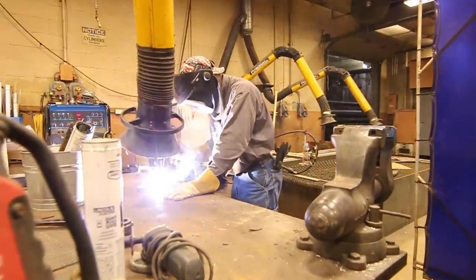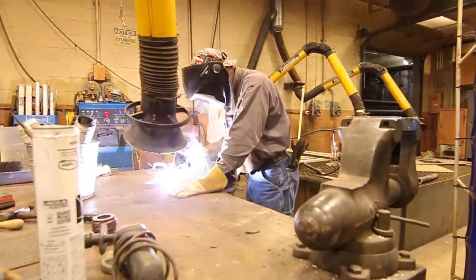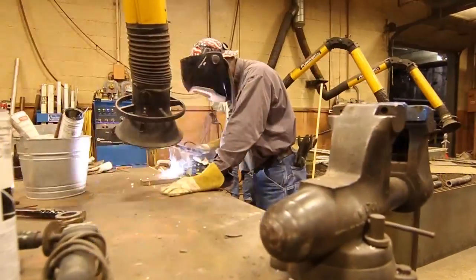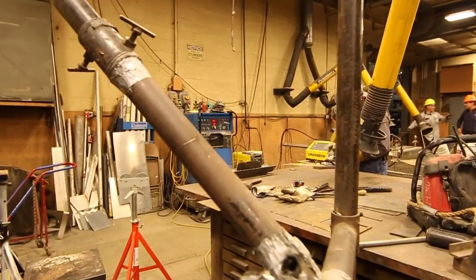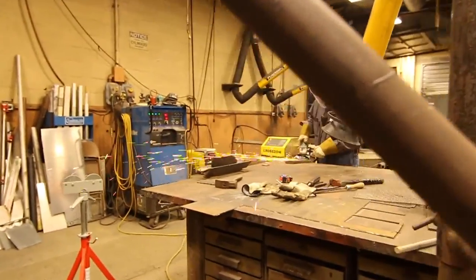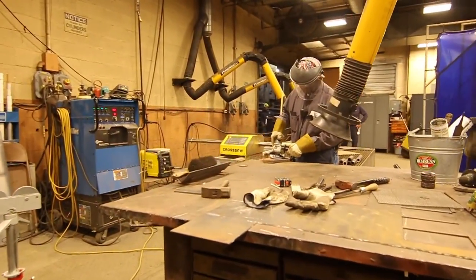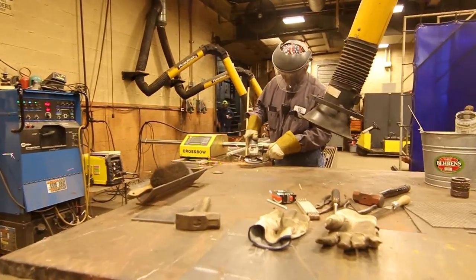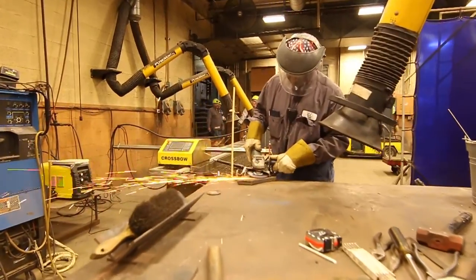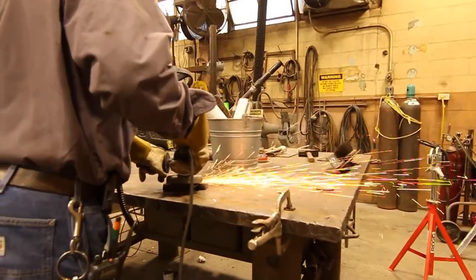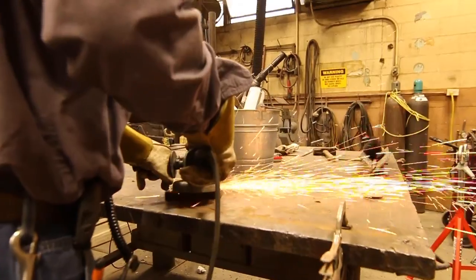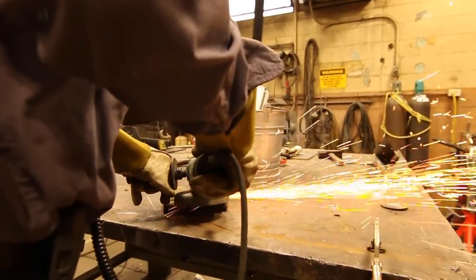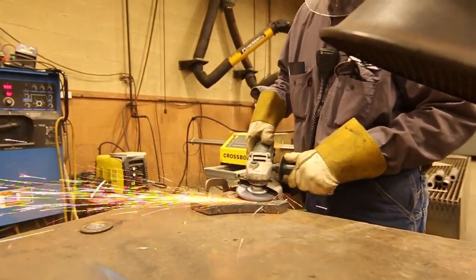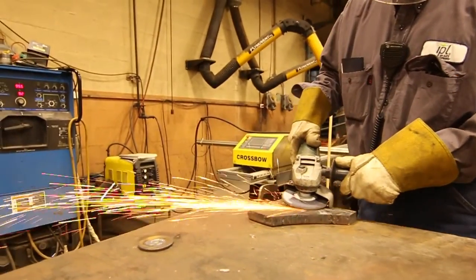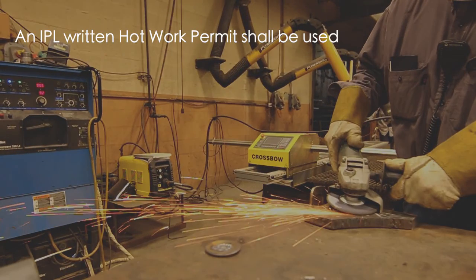Hot work. Contractors performing welding, cutting, burning operations, or spark-producing grinding shall comply with all state and federal regulations and IPL requirements, including but not limited to the following. It is important to note that this facility consumes large amounts of natural gas. Initial air monitoring is required before conducting any hot work. An IPL written hot work permit shall be used.